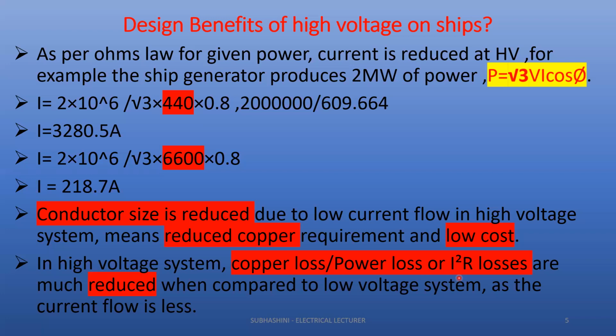So when we go for an HV system, the two major advantages we are seeing from this slide are: when the voltage is stepped up from 440 volt to 6600 volt, the current is getting reduced from 3300 to 218 amps. So we see the change. A vast difference is there. Because of this reduction, the conductor sizes are reduced and the cost is getting reduced. So this is the main advantage. And the losses are also getting reduced. I square R, the square of the current. Current is reduced, so losses are also reduced. That is the major advantage. We'll move to the next slide.